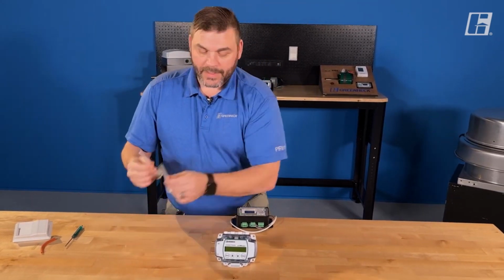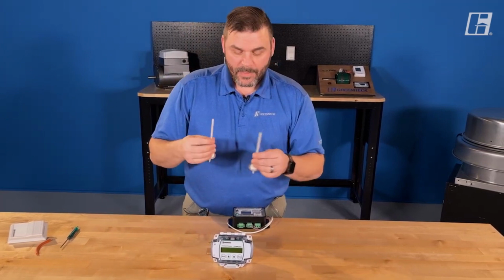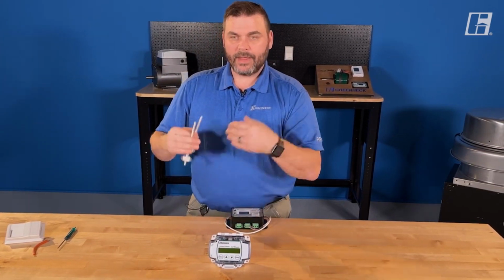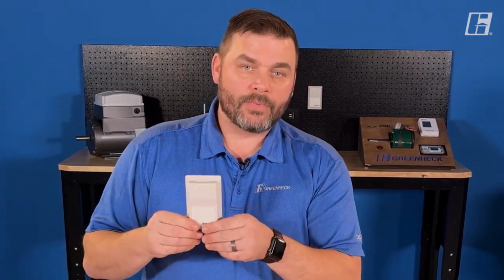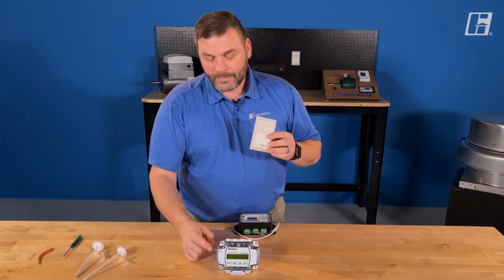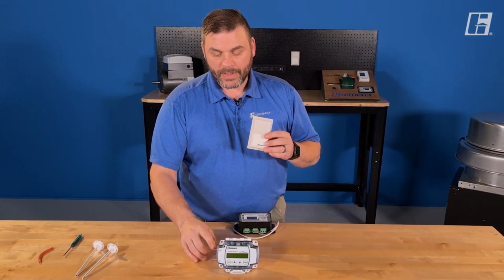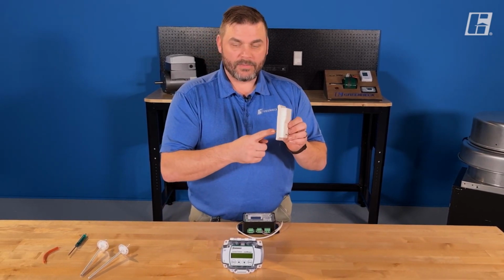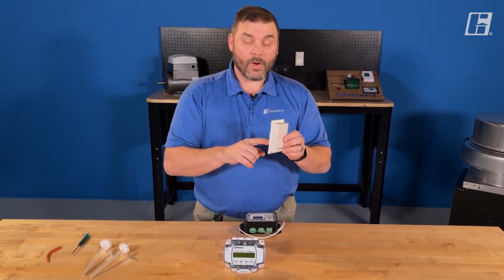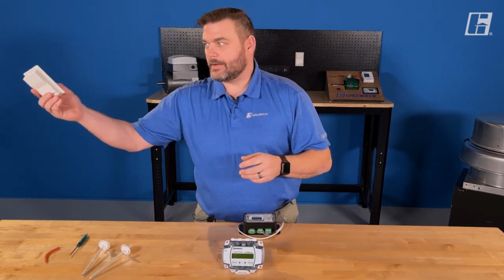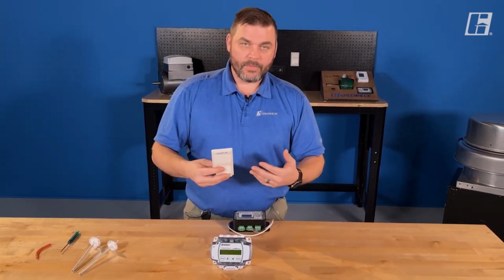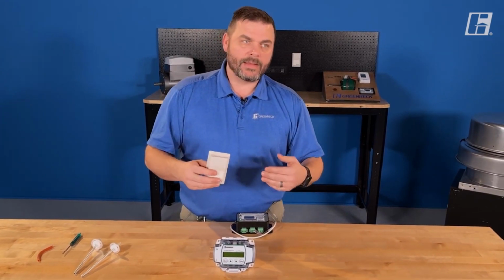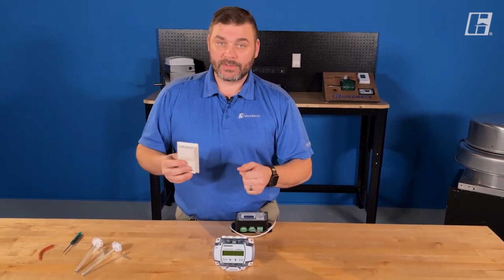So these two probes right here together, commonly called a pitot tube, will allow this device to maintain a specific CFM. But if I wanted to control the pressure between one room and another room, or a room and a hallway, I could simply use a room probe, right? And there's up to 100 feet of 1/4 inch tubing that can run from here to where the probe is installed. So I could have one of these in the hallway, I could have one of these in this room. Now I can actually program and maintain the pressure differential between the two spaces.